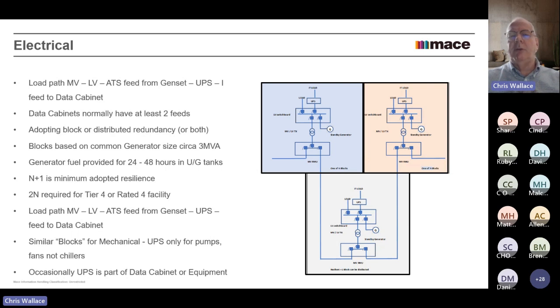So basically, in and out at MV, with a feed off to a transformer, after the transformer into a low voltage switchboard, and then out of the low voltage switchboard, you have an ATS, an automatic transfer switch, to a generator. Obviously those two incoming breakers are interlocked, so you'll have either the generator or the feed from the transformer, but not both. Then you'll have a feed out to a UPS for the IT load, and then maybe a non-UPS supported load, which might be a mechanical system of some sort, a pump or a fan, something that isn't mission critical.